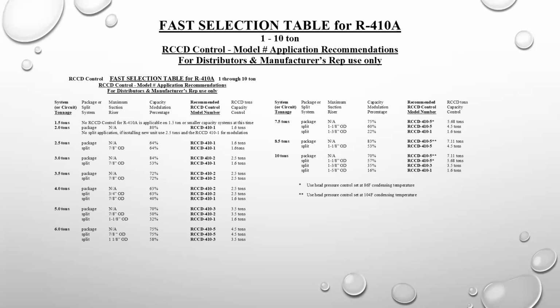It can go higher. Remember, a lot of systems, like a 20-ton package unit, could have two 10-ton compressors. So now all of a sudden, that 20-ton package unit with a 5 on it, giving you 7 tons of modulation, you're able to go from basically 3 tons to 20 tons with just a little bit of a gap in between.